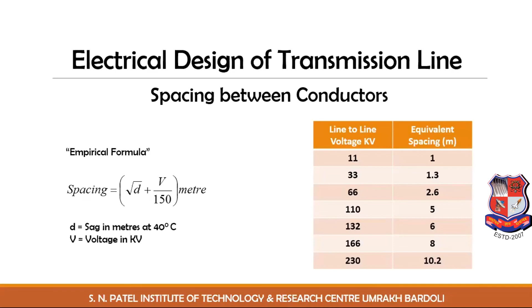For snowfall, the horizontal configuration of conductors is most suitable. In the table, we can see two columns: line to line voltage in kV and equivalent spacing in meters. Here for 11 kV, the equivalent spacing is approximately 1 meter. For 33 kV, it is 1.3 meters. Similarly as we move further, like 66 kV, 110 kV, 132 kV, 166 kV, and for the last, 230 kV, the equivalent spacing is 10.2 meters.